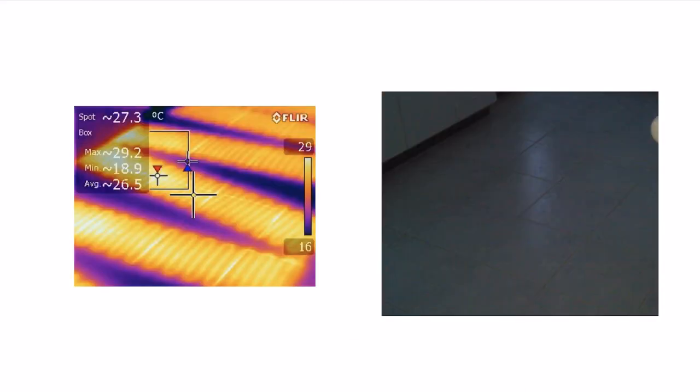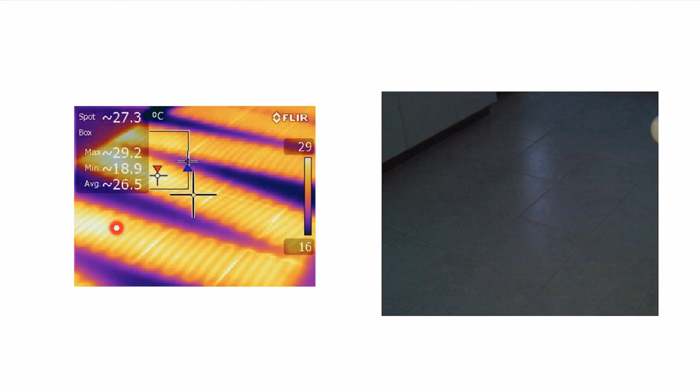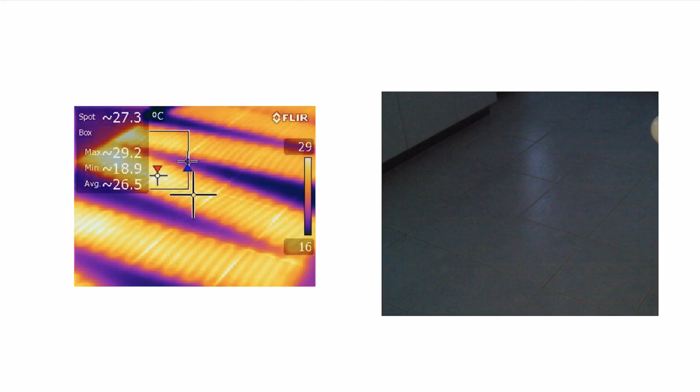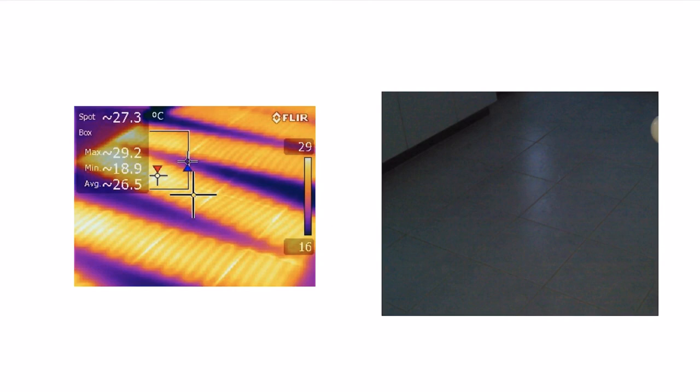Here's an interesting shot of the bathroom floor in the house during the same house inspection. Nothing in the visual image, but I turned on the in-floor heating. Very quickly, before you can even feel the heating on your feet, you can see the heating coils in this floor. You can see another issue when you're looking at your house inspection—they cut some corners in building this floor. These pads of heaters should be laid out side by side without this gap between them. They've saved a little bit of money by putting these out on an angle in a W pattern instead of laying them out side by side. It means that when your nice in-floor heating is on, you have a rather large cold spot on the floor about the size of your foot. You can be standing in there with one foot hot and one foot cold. This is something they obviously never should have done, and it was good to know that before actually buying the house.